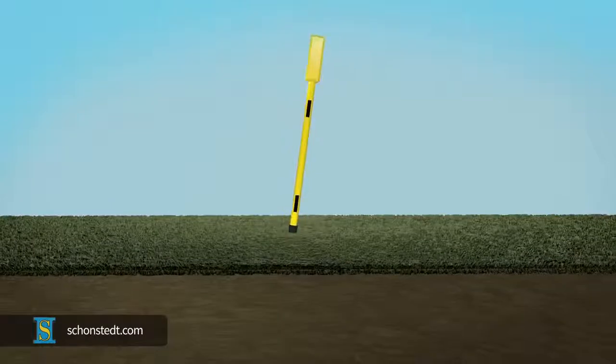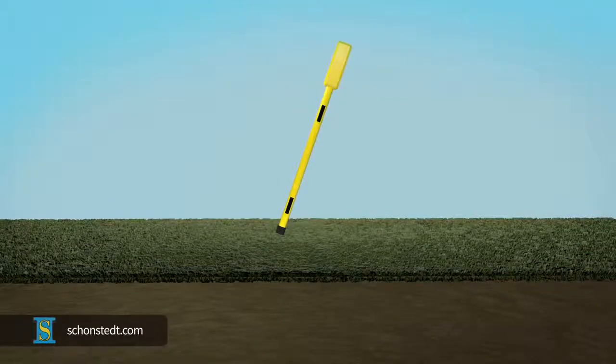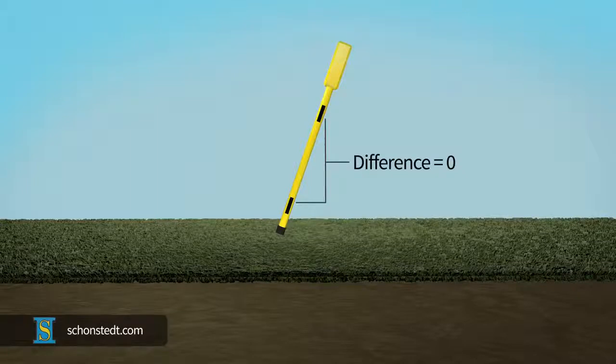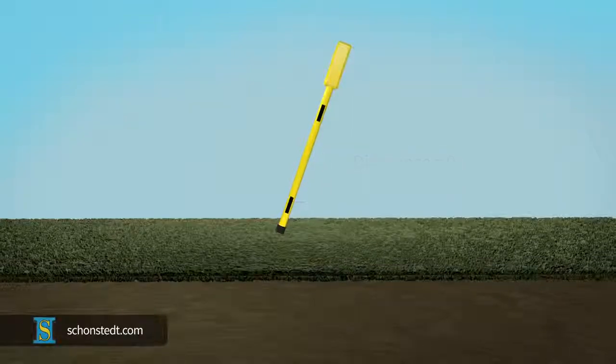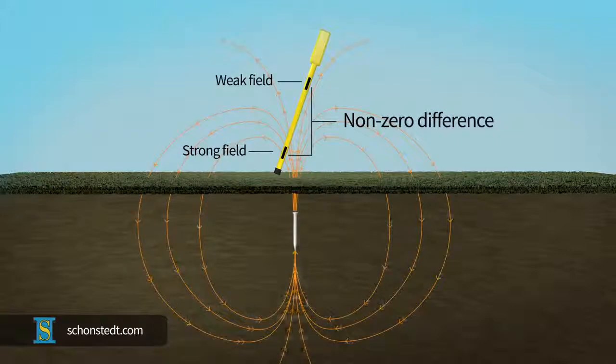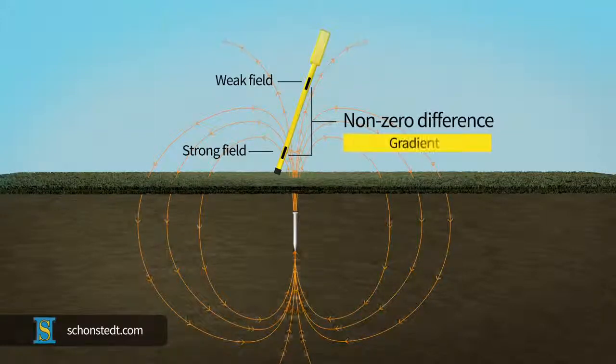Schonstedt magnetic locators operate on the principle of detecting the difference in the magnetic field present at two sensors spaced a fixed distance apart. In the absence of a buried object, the field at both sensors is the same. The presence of an object made of iron or steel results in a difference between the magnetic field at the top and bottom sensors. That difference is called a gradient.